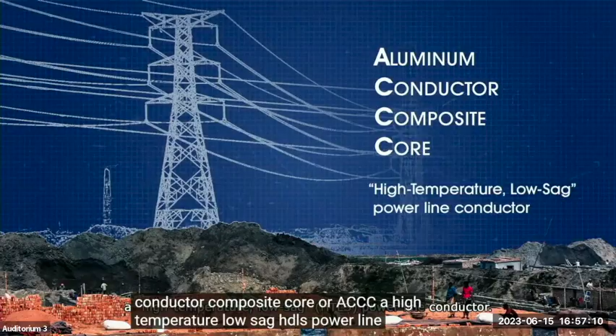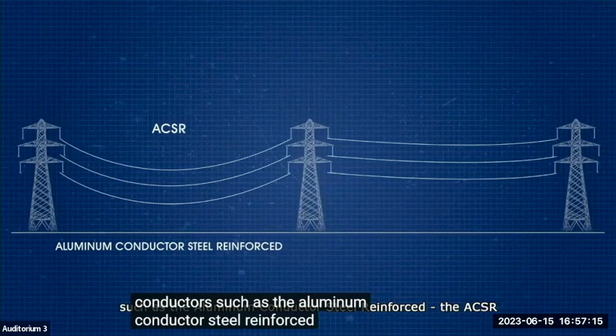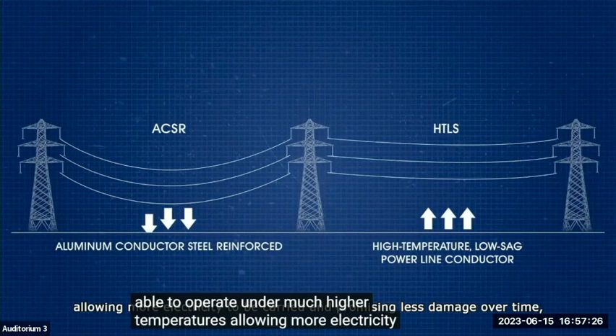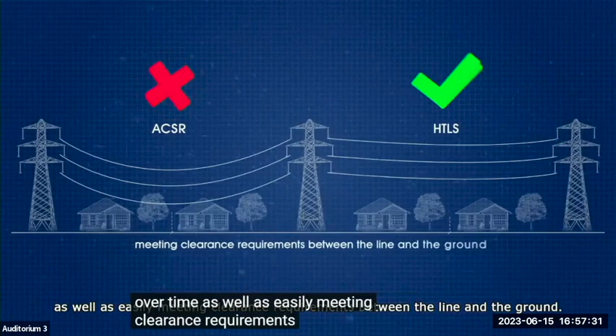The project aims to modernize the energy infrastructure of the country by using 2 advanced technologies. Firstly, the project will fund the use of advanced conductors called Aluminum Conductor Composite Core, or ACCC, a high-temperature, low-sag HTLS power line conductor. Compared to conventional conductors such as the Aluminum Conductor Steel Reinforced, the ACSR, these new high-temperature, low-sag conductors reduce thermal sag by operating under much higher temperatures, allowing more electricity to be carried and promising less damage over time, as well as easily meeting clearance requirements between the line and the ground.